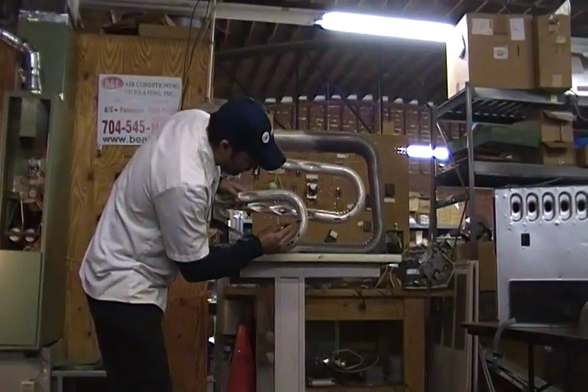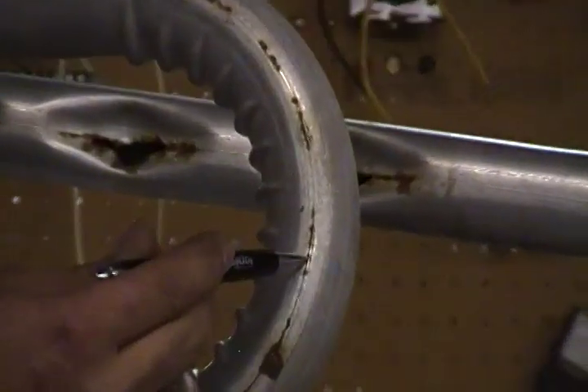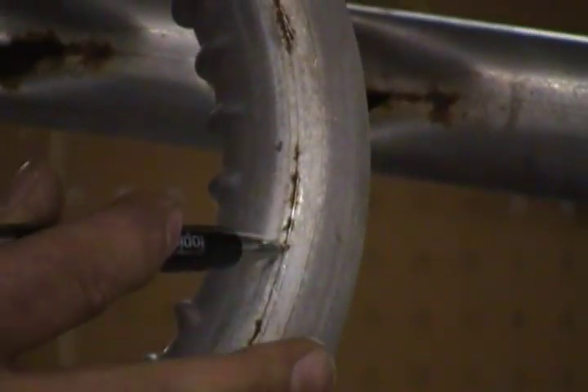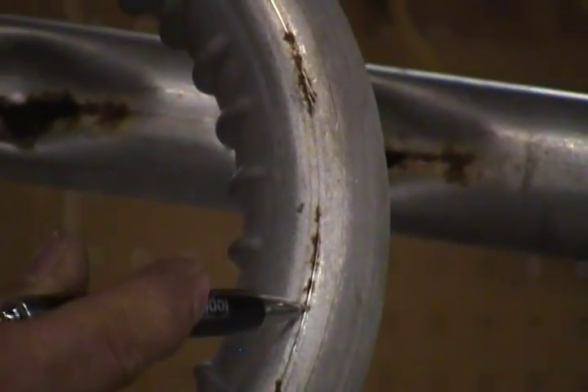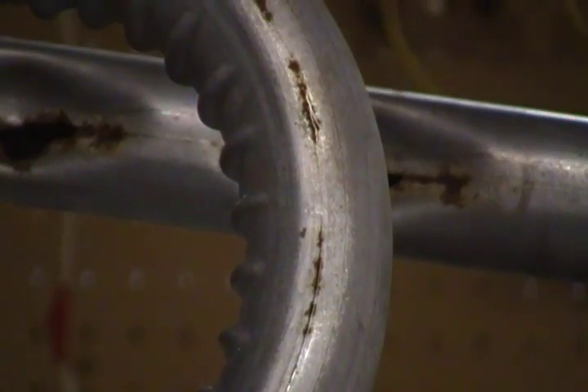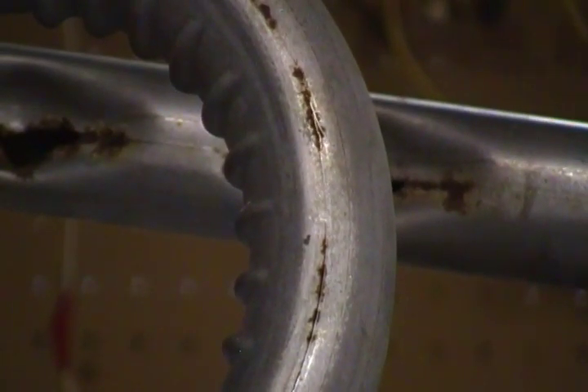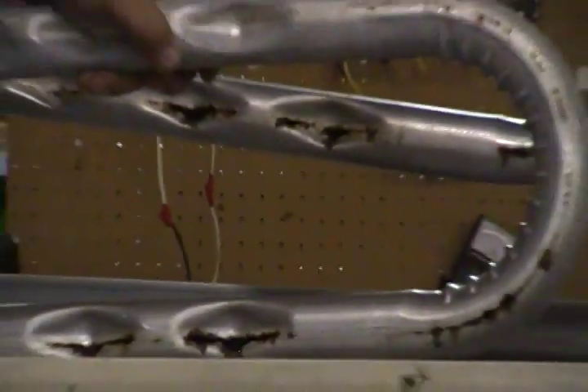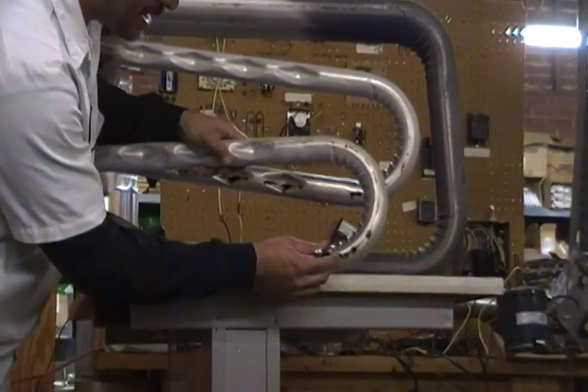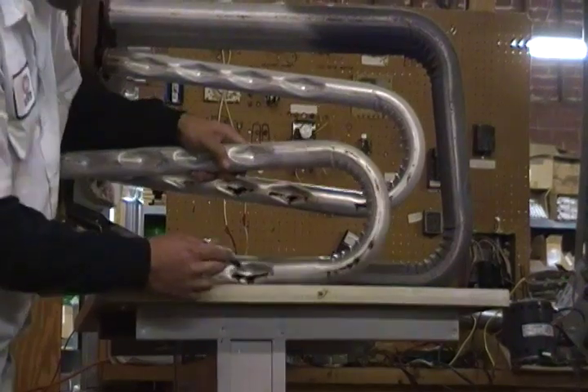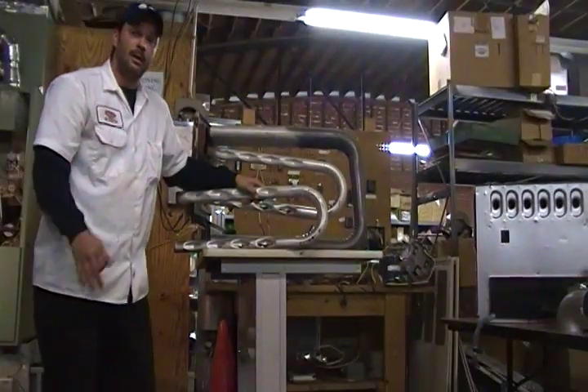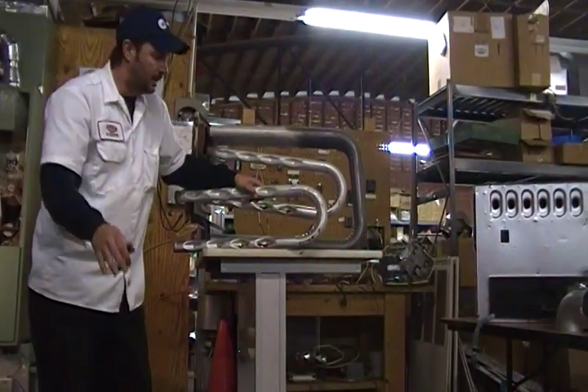If you look at these fine seams, those are cracks. You could actually slide small material between that. You could come in here - this was not rusted through all the way, and I did that with the tip of my pen. If you can come in on a heat exchanger and inspect it with a pen, and literally the rust flakes off before you, chances are you're in severe need of replacement.